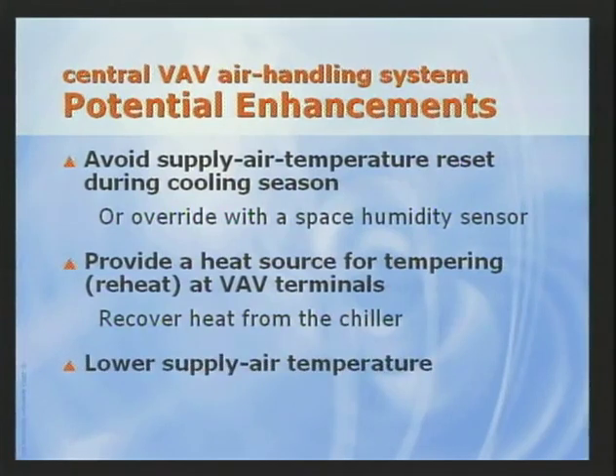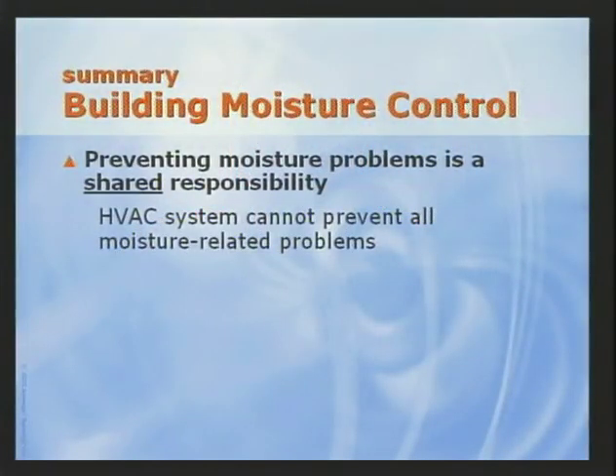And third, investigate the use of colder supply air. Lowering the supply temperature reduces supply airflow and results in more moisture condensing on the coil and lower space humidity levels. Now, in summary, the HVAC system, again, cannot prevent all moisture-related problems in buildings. This is a shared responsibility among all parties involved in the design, construction, maintenance, and use of the building.